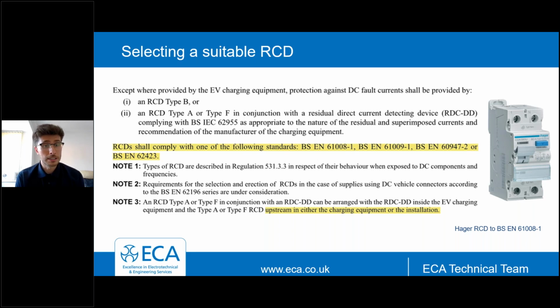We need a suitable type of RCD, and this RCD shall meet one of the following standards. This is a shall requirement, which means it needs to be fulfilled in order to achieve compliance with the regulations. So we urge members to confirm that the RCDs that they're selecting meet the relevant British and European standards as required by this regulation. So some EV charging equipment has inbuilt RCDs. So if your EV charge point that you're installing or specifying has an inbuilt RCD, you need to confirm that this RCD meets one of these standards.